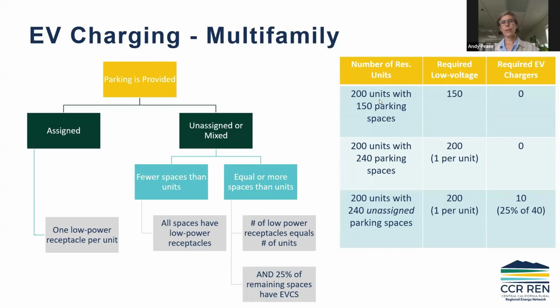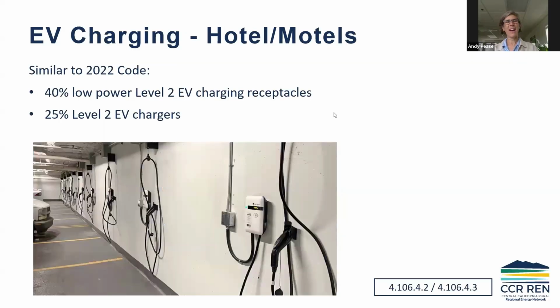Here's the example. If you have 200 units but only 150 parking spaces, you need 150 low voltage receptacles, and no chargers. With 200 units and 240 parking spaces, you need 200, you don't have to go more than that. But because all of the spaces are assigned to units, it still doesn't retrigger EV charging. But if you do 200 units and they're unassigned, then that maxes out at 200, but whatever is not a unit count does need chargers. I apologize if that is a lot, please reach out to the code coach if you have a specific instance.